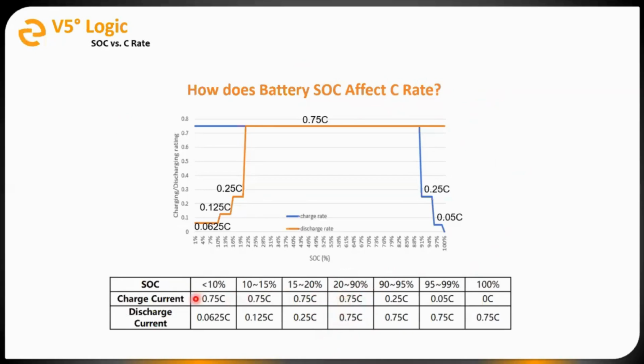As we get to lower state of charge, aka we're discharging the battery, the discharge current is going to start to limit more and more, closer to zero, while the battery charge current will remain the same. The opposite happens going towards 100% SOC. We can see that our charge rate decreases as we get closer to 100, and then the discharge rate stays that same 75 amps all throughout.